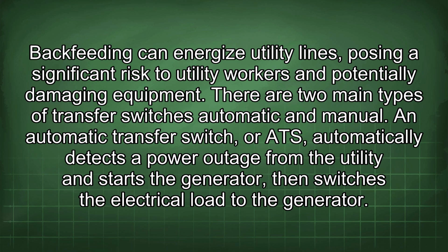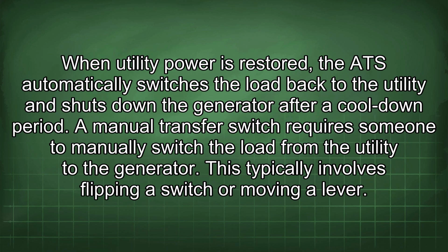There are two main types of transfer switches: automatic and manual. An automatic transfer switch, or ATS, automatically detects a power outage from the utility and starts the generator, then switches the electrical load to the generator. When utility power is restored, the ATS automatically switches the load back to the utility and shuts down the generator after a cool-down period.